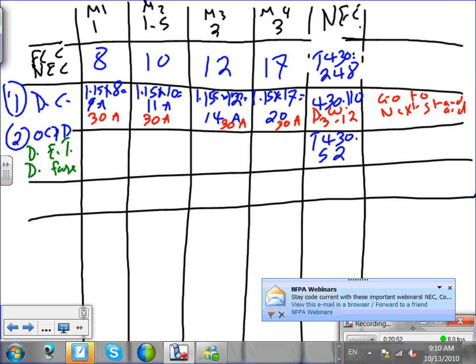What is your opinion on, let's say you're an amp over, you're at 21, would you go up to 25? If you read this table, guys, you're allowed to, sure. Yes, you're allowed to. Unless I know otherwise, I would go up. Unless I do overcurrent protection device coordination, which you guys are going to be doing, until I do that, I always go up. It's a cover yourself.